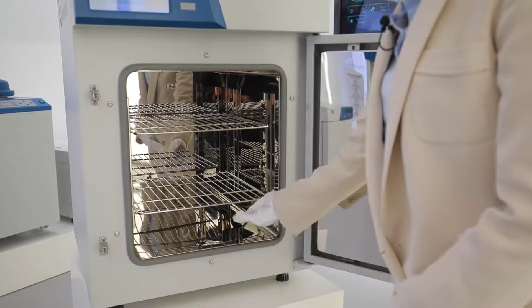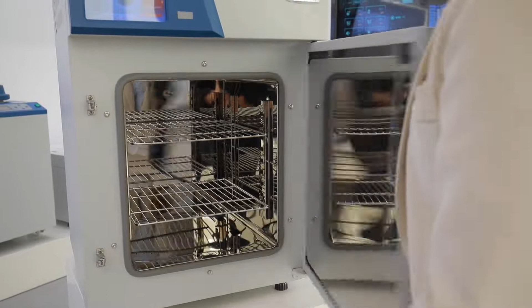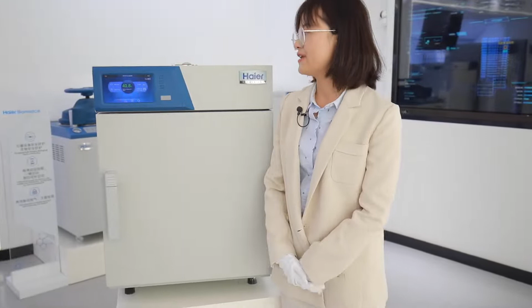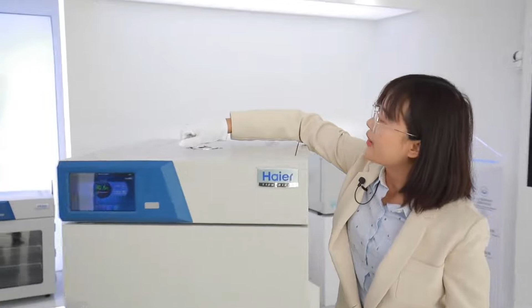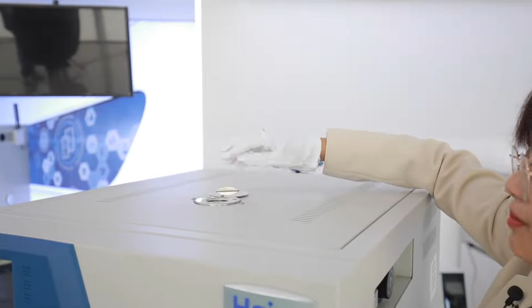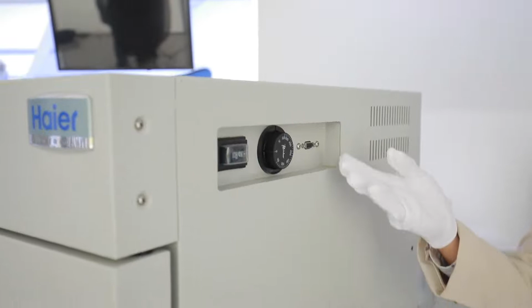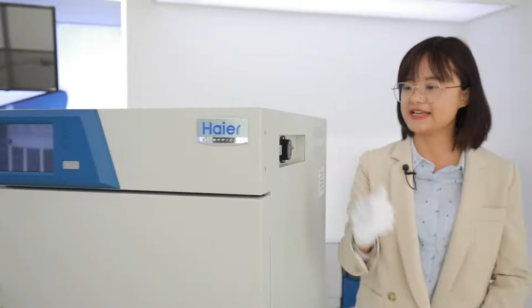All the heating tubes are in the bottom plate and also on the left side and the right side. On the right top, a 7-inch touchscreen is installed for the monitoring and setup of all the meters. The feet underneath can be adjusted. On the top of our cabinet, here is a test port. All the cables of the measurement instruments can go through here. And on the left side of the cabinet, all the switches and interfaces are here. This is the power supply switch, this is the over temperature switch, and this is the RS485 interface. That's all for our cabinet. Let's get back to our slides.